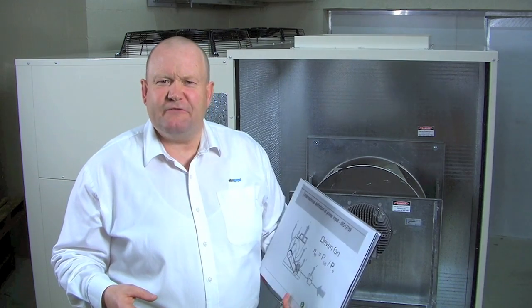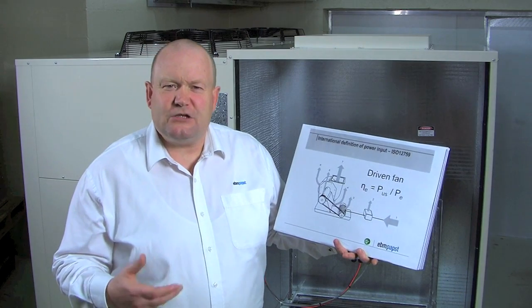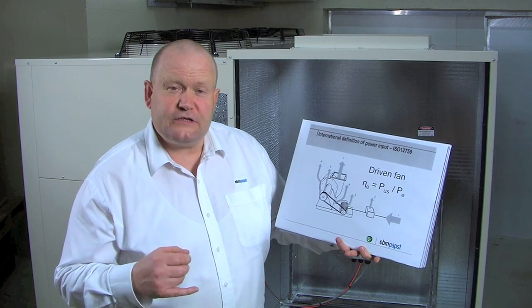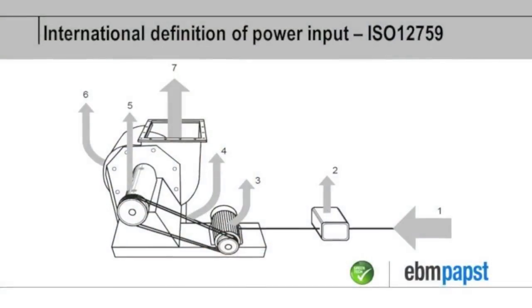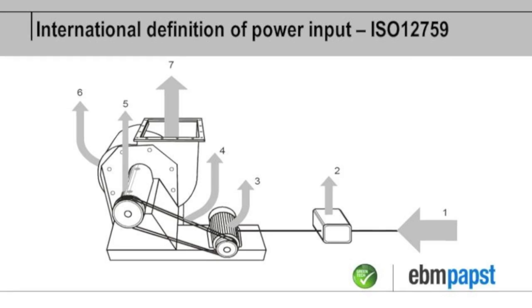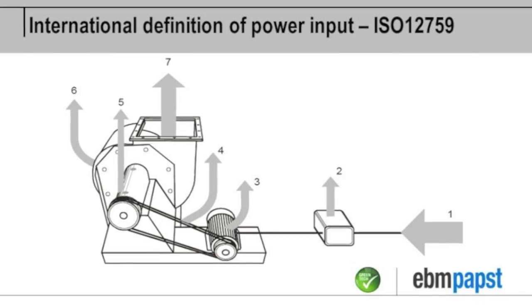The standard that's been used to create these regulations is ISO 12759, and here I've got a slide showing the definition of fan efficiency in that standard. Here you can see that the fan is taken as a system as a whole and the efficiency is the divisor between the fan input power to the whole fan system and the air output power.